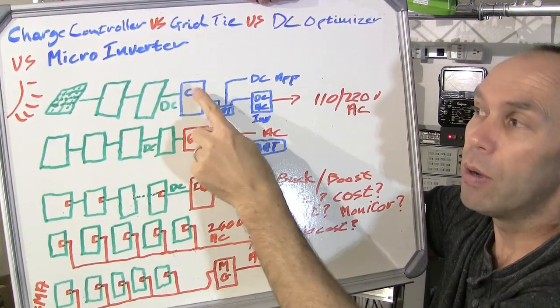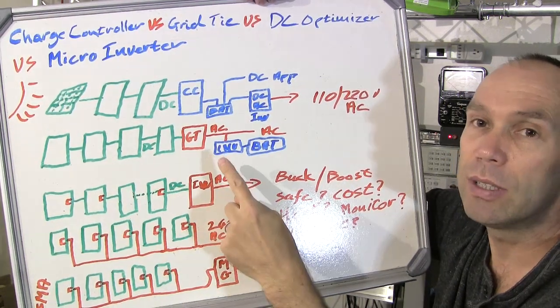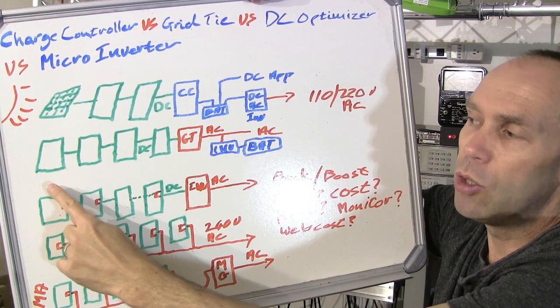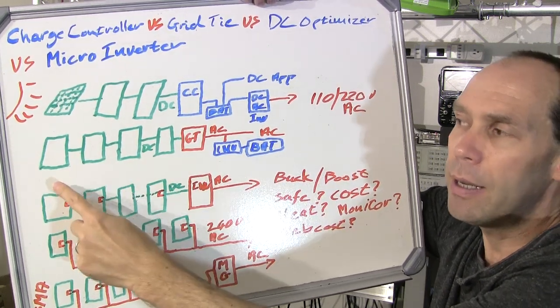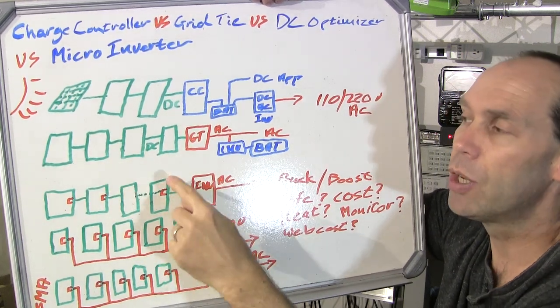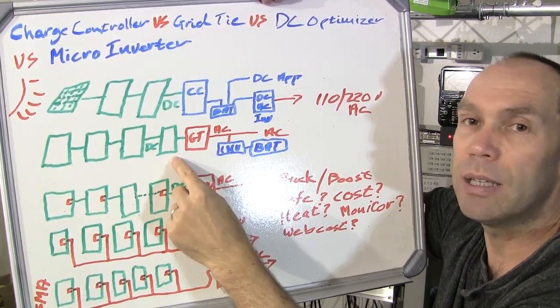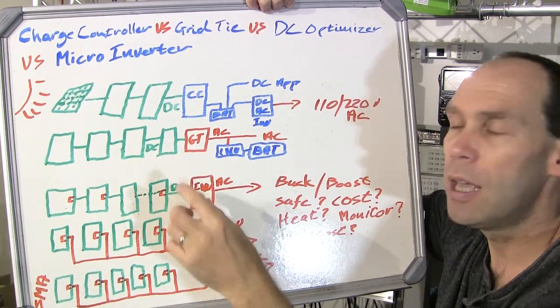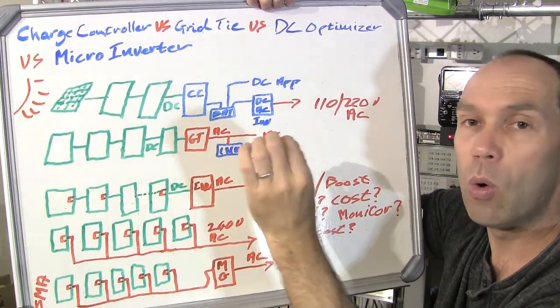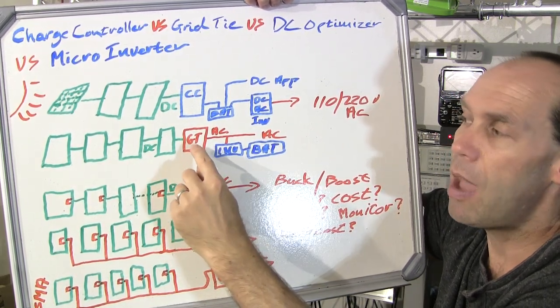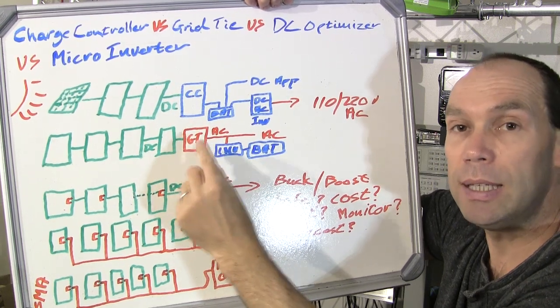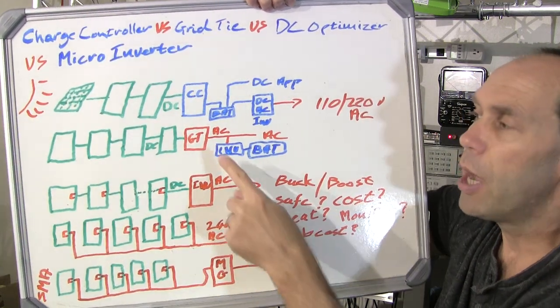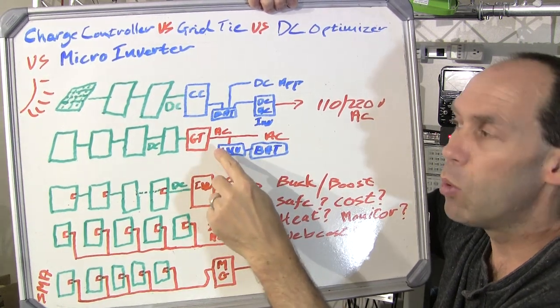Now let's talk about the grid tie solution, which is probably one of the most common installations happening today. You have a string of panels and the idea is to string quite a few panels together to get a higher voltage. A higher voltage is beneficial in two regards: first, it means less current has to be carried by the wires, reducing losses; and second, your grid tie inverter will have a better time inverting a higher DC voltage to the higher AC voltages required for households. If you're in a normal household where your appliances are AC, this would obviously seem like the more logical route to go.